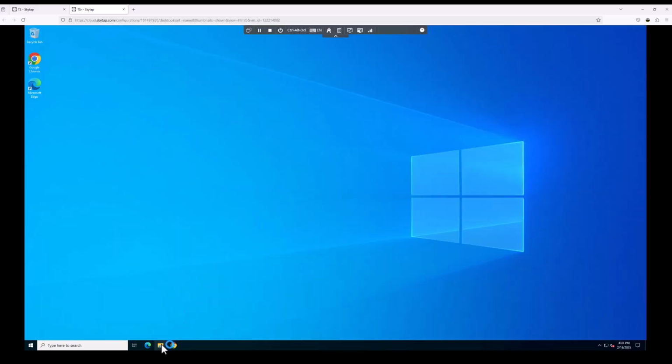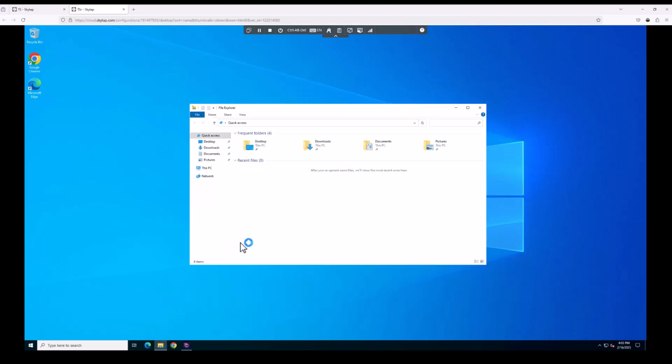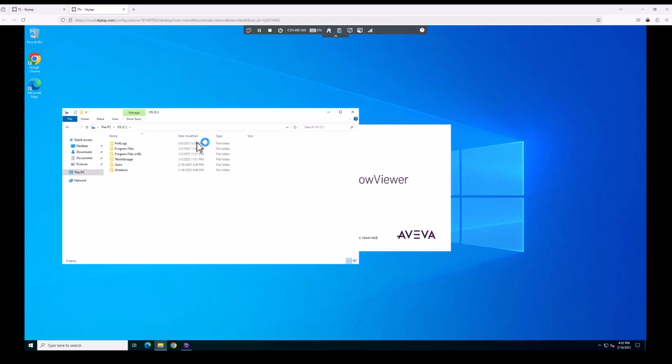Now I do a find, and because I'm specifying a network path when doing the find, InTouch understands that it's going to need to copy the app to the NAD folder. It understands it to be a NAD application. I could have other apps, I could have local apps, which we'll see here in a second, that I'm just working on that are not NAD. But if I'm doing the network location, it'll recognize it as a NAD app.